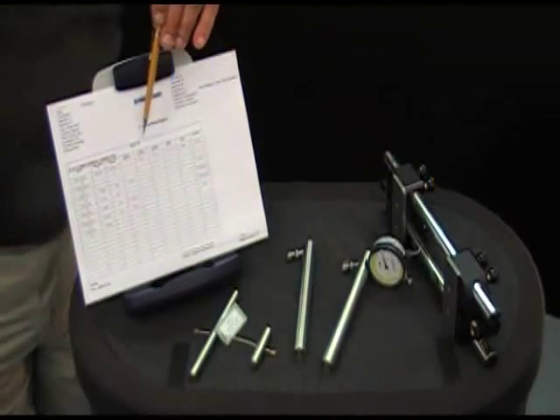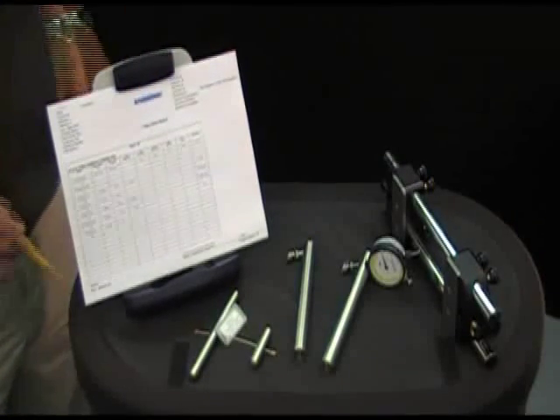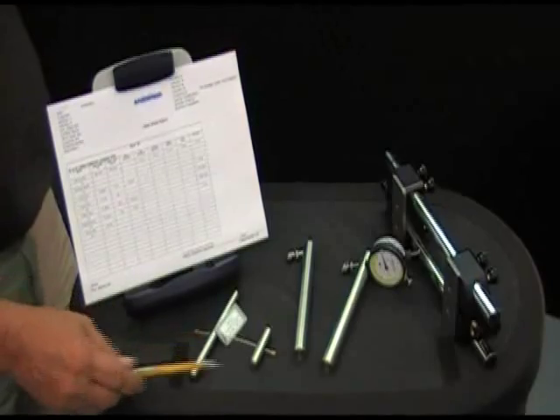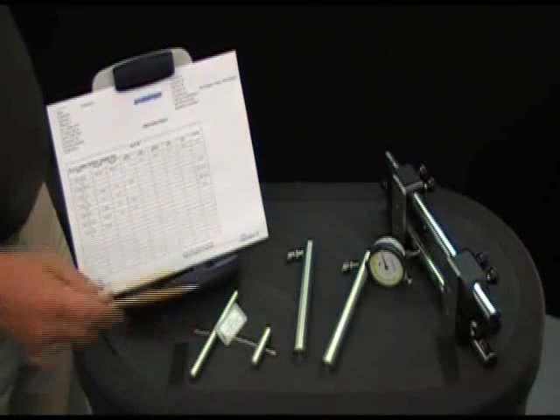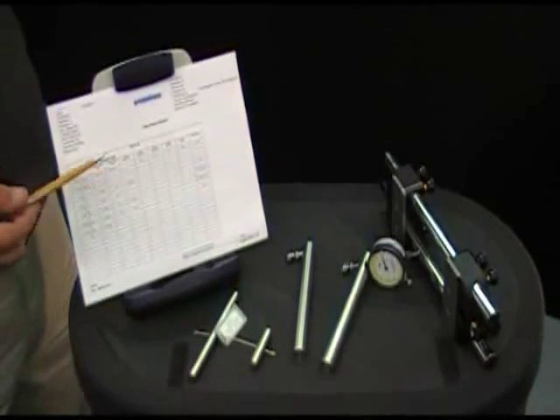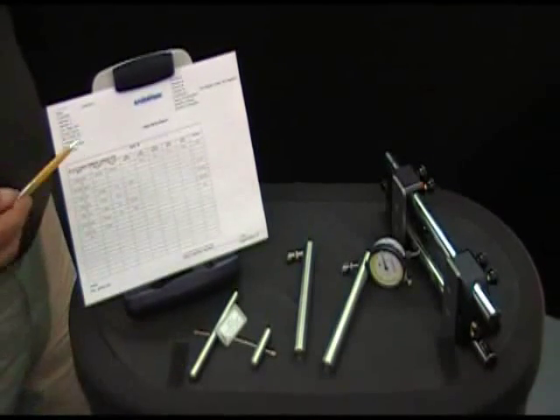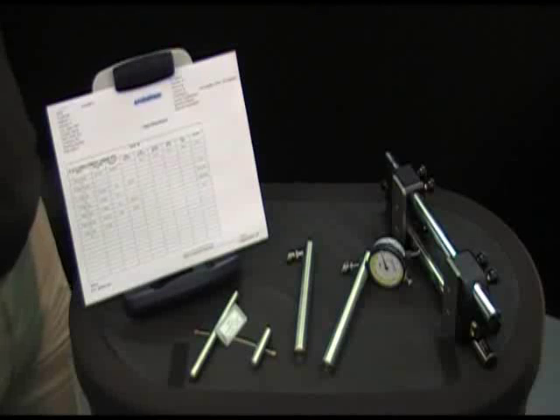Over in the rod setting standard, it shows us the proper A dimension and B dimension setup for the gauge. This is very critical that we have this so that we can document the serial numbers of our standards and our gauges to show traceability of our calibration.